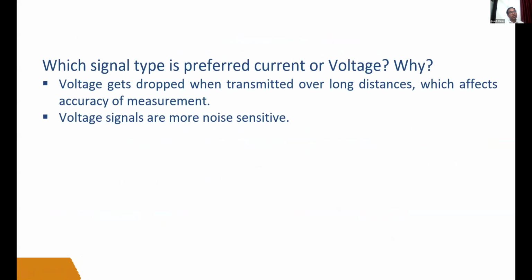Why? Because voltage gets dropped when transmitted over long distances, which affects the accuracy of measurement. Voltage signals are also more noise sensitive. So my suggestion is that if you want accurate output, or if the system is very sensitive, we must prefer the sensor which provides the output in the current form.